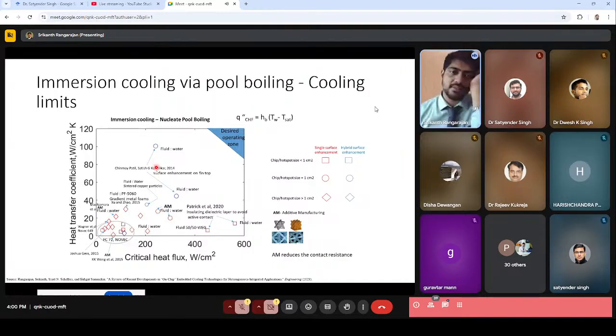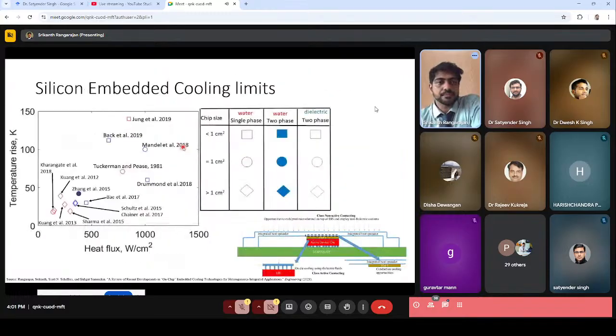The points grouped at the bottom left, corresponding to very low critical heat flux and low heat transfer coefficient, are mainly from dielectric fluids. Most of these points occur where the chip hotspot size is less than 1 square centimeter, though some correspond to a hotspot size of 1 square centimeter or greater. This shows that liquid water has huge potential even for phase change cooling, but the problem is you have to stop the interaction between the active electronic circuits and the liquid water.